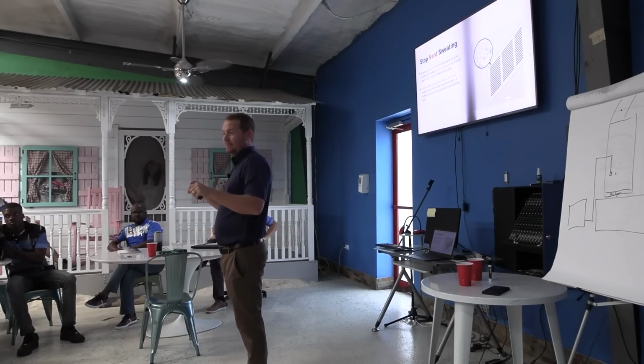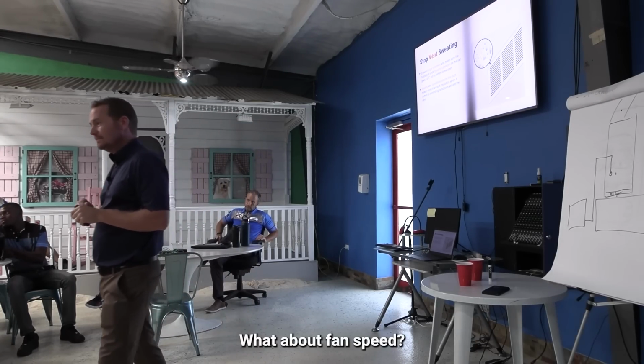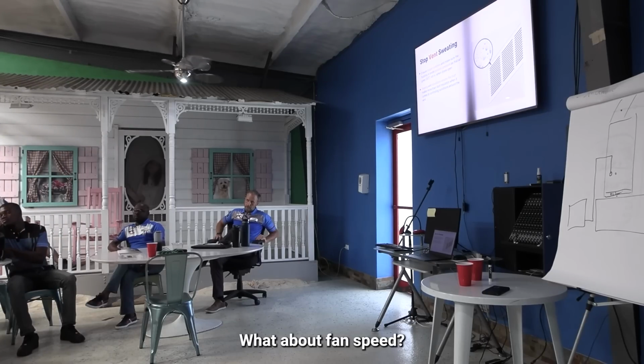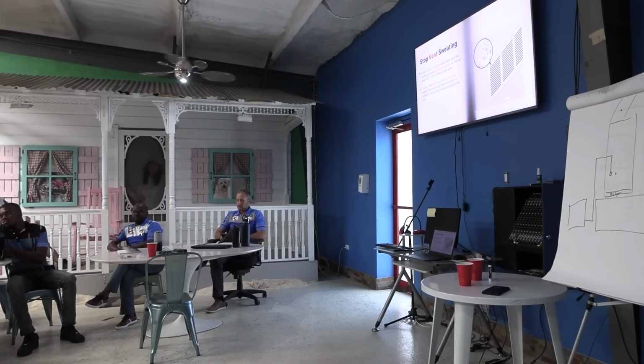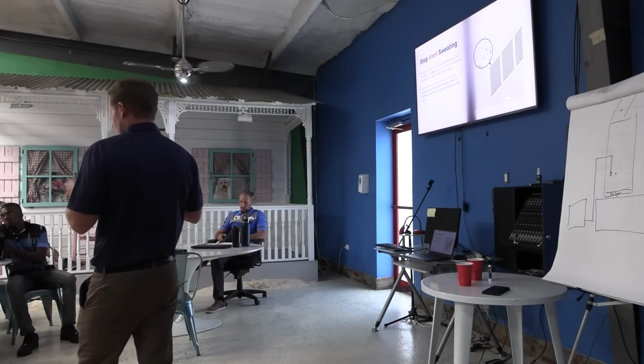Yeah. Go ahead. What about the fan speed? Well, fan speed results in colder or warmer evaporator temperature, right? If we increase fan speed, what happens to the evaporator temperature? Goes up. So what happens to the ability to dehumidify the whole house? Goes down, right? So if we drop fan speed, that makes a colder coil. That's what that does, right?